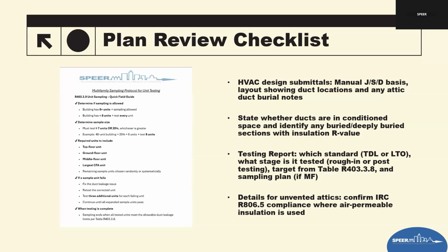If the design is calling for buried ducts or deeply buried ducts, which again we probably won't see in Texas, you want to know what the duct insulation is and what the insulation that will be surrounding and on top of the ducts is. Those details need to be listed on the plans themselves for plan review.